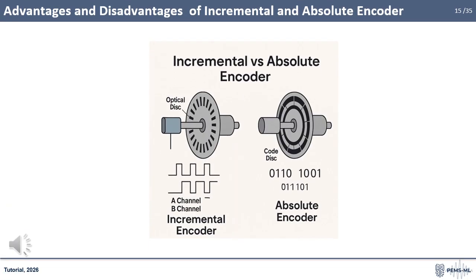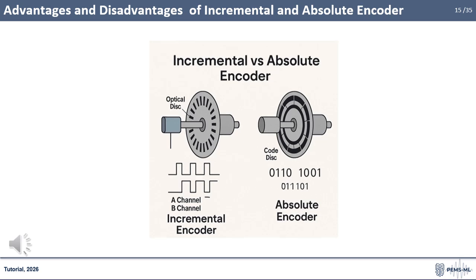An incremental encoder is easy to manufacture and cost-effective for customers, while also being able to determine the speed and direction of motion. However, since all marks in a row are identical, it requires setting a reference point for position determination. Additionally, position information is lost when the electrical power supply is interrupted. An absolute encoder determines the exact angular position without requiring a reference point, and it retains position information even if the power supply is lost. However, it is more complex and expensive to manufacture, which results in a higher overall price.